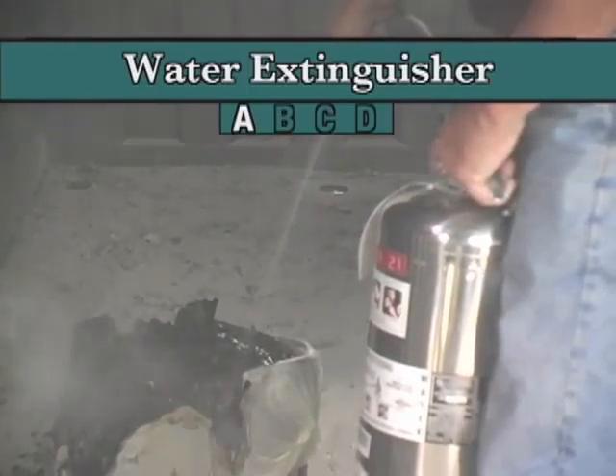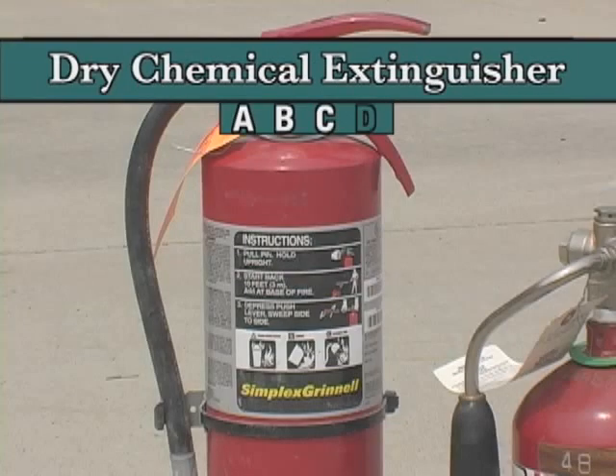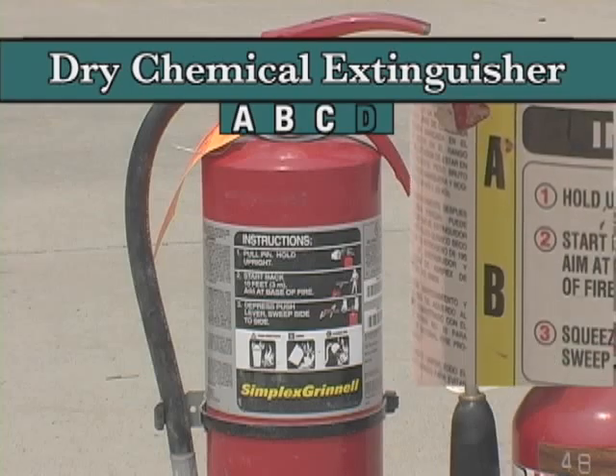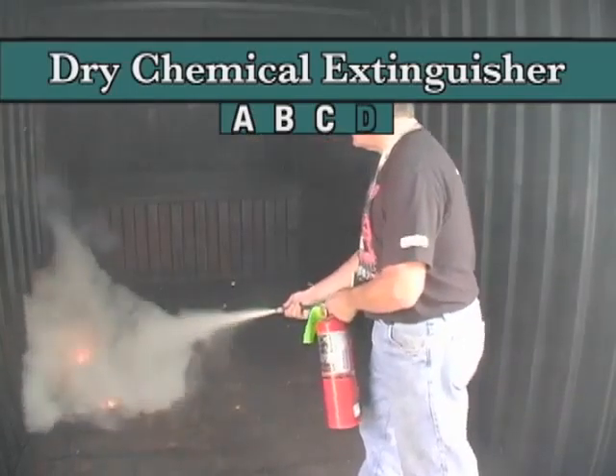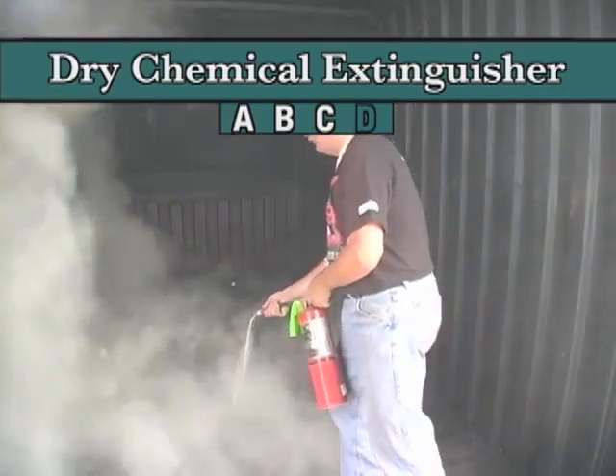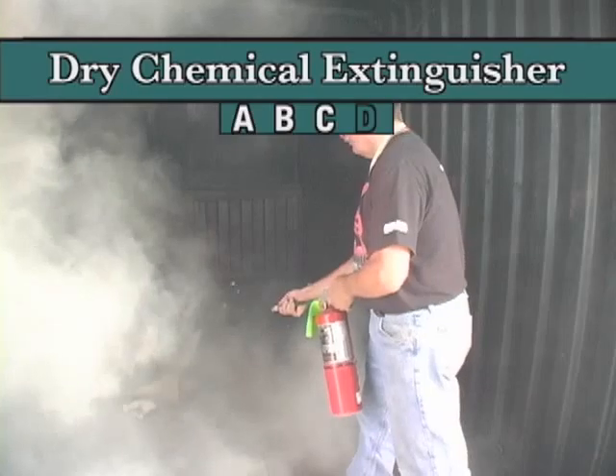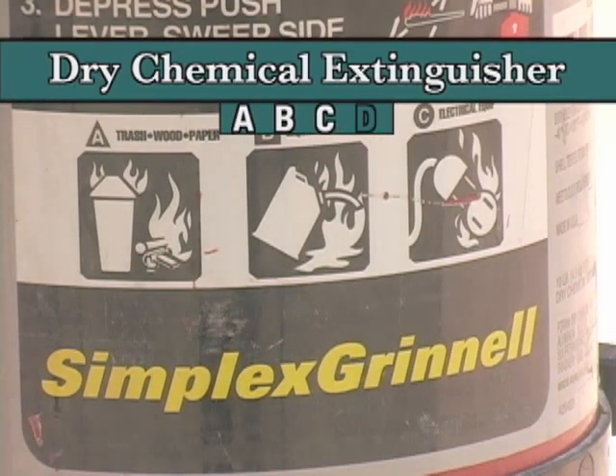Fight the fire with water if you're sure it only involves ordinary combustible materials like paper, cardboard, or plastic. Dry chemical extinguishers come in a variety of types and are suitable for Class A, B, or C fires. These are filled with foam or powder and pressurized with nitrogen. Check the label to see what kind of fire the extinguisher is designed for.